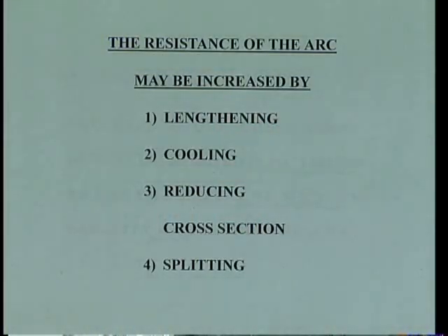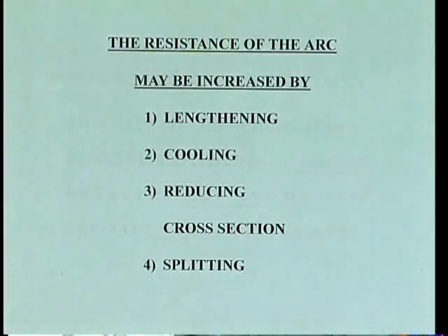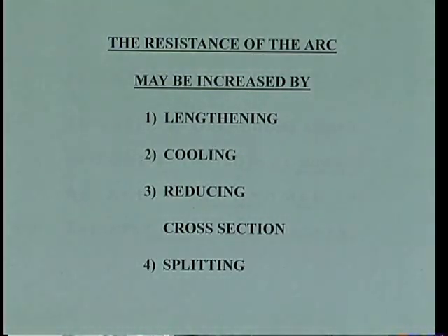And the fourth one is splitting the arc. Here the arc is split into a number of smaller arcs in series. In this way the arc is first lengthened and then cooled. So splitting means the arc is lengthened and split. Both lengthening and cooling of the arc increase the resistance of the arc.